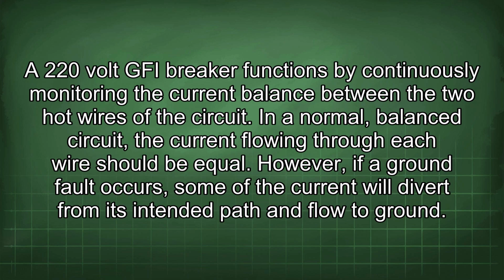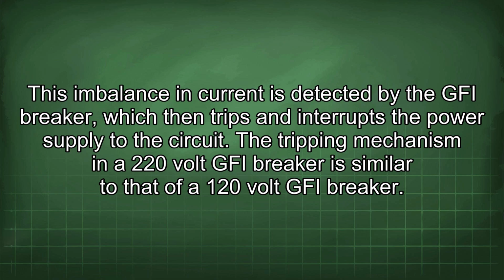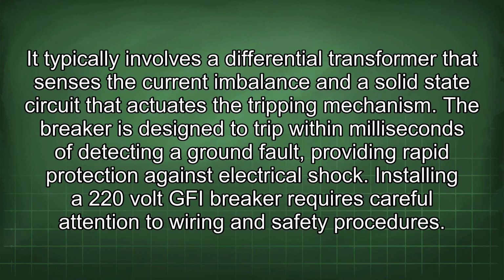A 220-volt GFI breaker functions by continuously monitoring the current balance between the two hot wires of the circuit. In a normal, balanced circuit, the current flowing through each wire should be equal. However, if a ground fault occurs, some of the current will divert from its intended path and flow to ground. This imbalance in current is detected by the GFI breaker, which then trips and interrupts the power supply to the circuit. The tripping mechanism in a 220-volt GFI breaker is similar to that of a 120-volt GFI breaker. It typically involves a differential transformer that senses the current imbalance and a solid-state circuit that actuates the tripping mechanism.